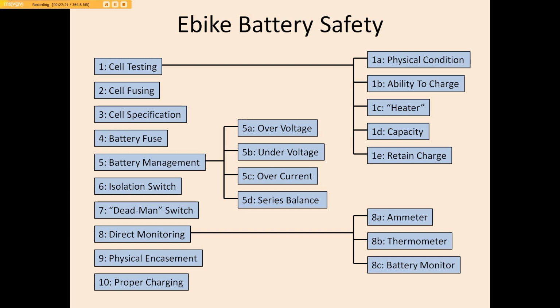So what I've done is bought a bunch of axial glass fuses, all rated at 3 amps. Now that may seem contradictory to what I just said, but keep in mind that these axial glass fuses actually blow at about twice their rating. So when you buy a 3 amp axial glass fuse, they don't blow at 3 amps — you can use them at 3 amps, and they blow at about 6 amps. They're slow blow fuses too.